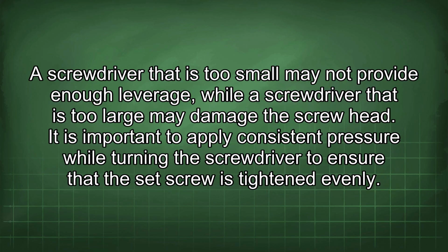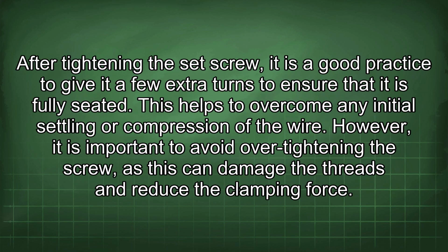A screwdriver that is too small may not provide enough leverage, while a screwdriver that is too large may damage the screw head. It is important to apply consistent pressure while turning the screwdriver to ensure that the set screw is tightened evenly. After tightening the set screw, it is a good practice to give it a few extra turns to ensure that it is fully seated. This helps to overcome any initial settling or compression of the wire. However, it is important to avoid over-tightening the screw, as this can damage the threads and reduce the clamping force.